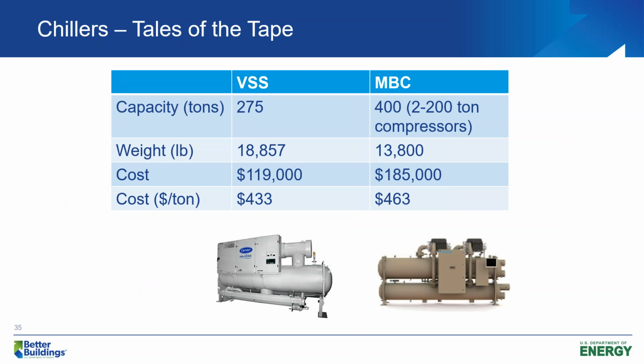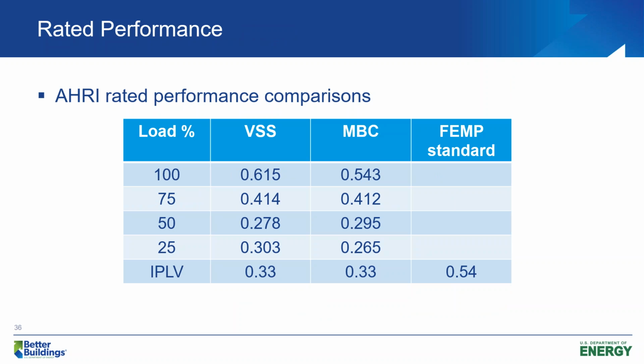So here's what we have, the two chillers. One was a 275-ton chiller, the variable speed screw chiller. The magnetic bearing chiller was actually a 400-ton two compressor chiller. So it's not a perfect direct comparison, but it's very close. And then you can see the cost, and the cost per ton of the two chillers is relatively similar. If you've ever purchased HVAC equipment, you're going to get a different cost every time you go out and compare, so you'll have to cost that for your own project, and you'll probably get a different price. If we look at the rated performance of the two chillers, they're nearly identical.